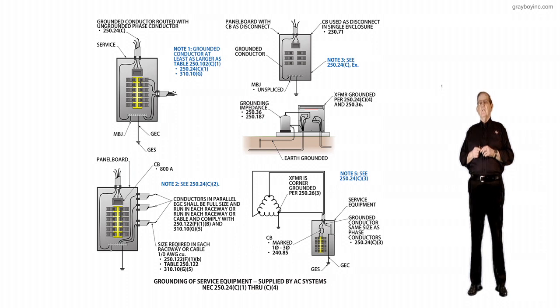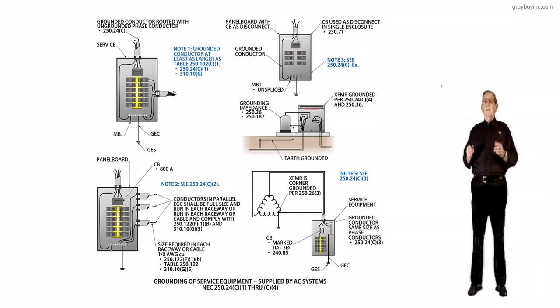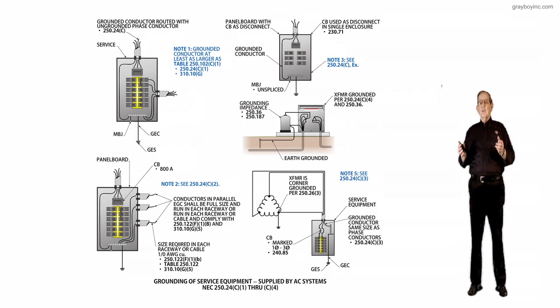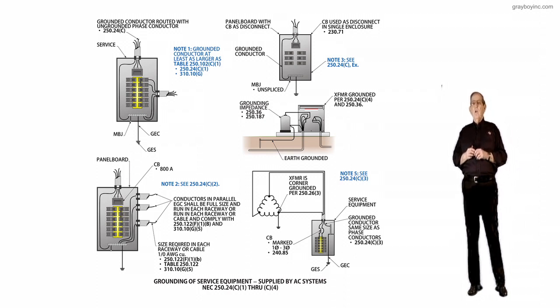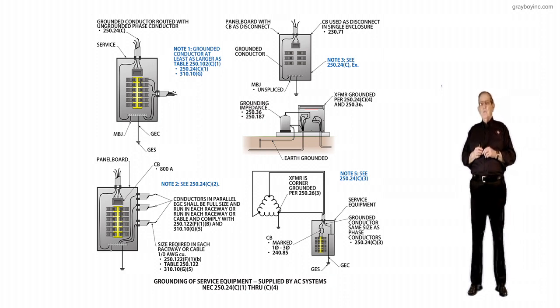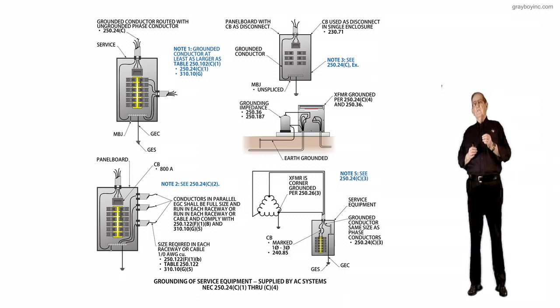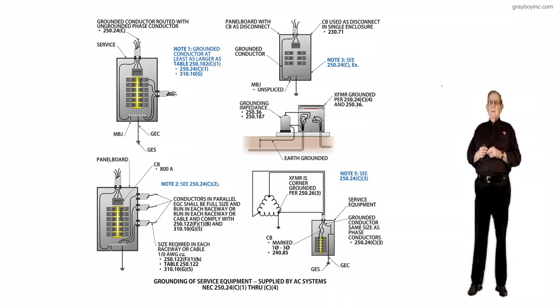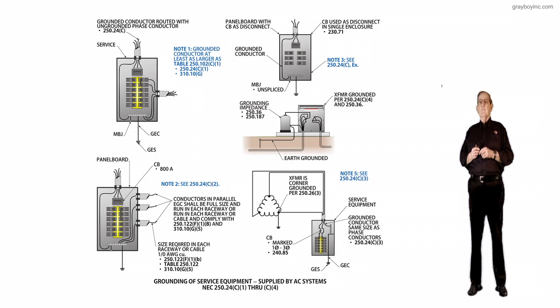And what an electrician should not do, and that's what this is trying to point out, is drop that grounded conductor just two sizes like the code used to list for the neutral conductor in a dwelling unit. And then commercial too, usually the neutral, or the grounded conductor, was a couple sizes smaller than the phase conductors because of all your phase-to-phase loads. But on this corner grounded system, they're calling that out in 250.24(C)(3). Don't treat it like that. Make sure it's the very same size or you'll be damaging equipment that is connected.